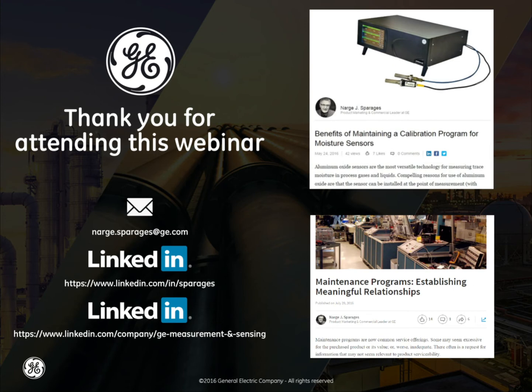So we highly recommend returning the sensor to the vendor's calibration facility, even if it is on another continent. At the same time, keeping a set of spare sensors cycled for those calibrations at least makes it easier from a time perspective so that you're not without a measurement when you need one. And that's where keeping track of that is an important function, and that's where certain tools can help, whether it be things like Instrument Calibration Portal in order to track your calibrations when you need them, or whether an exchange program might work locally.